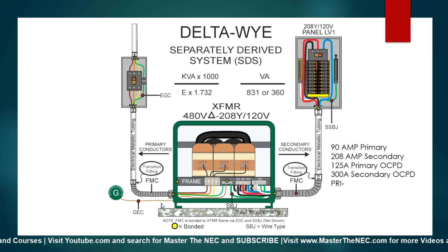But generally, you know, grounding electrode conductor, if it's a concrete encased electrode, it'd be no larger than a 4. If it's a ground ring, it doesn't have to be larger than a 2. If it's a water pipe ground or in-ground steel, then you're going to have to use Table 250.66. Now, 250.66(A) is for ground rods and plates and pipes that are used.